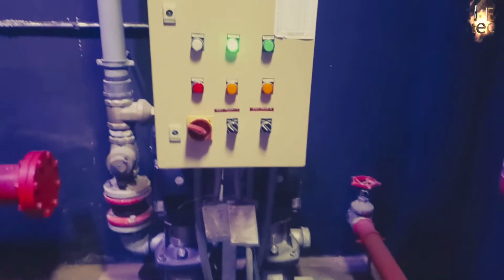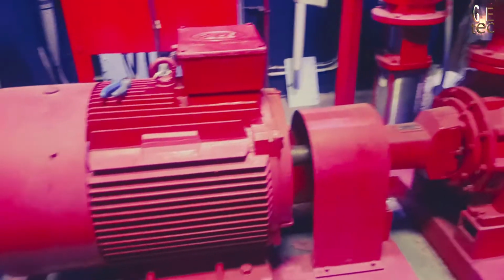Secondarily, this pump prevents sprinkler systems from being damaged when the fire pump begins sending water. If a system does not have a jockey pump keeping it pressurized, it may have a relatively low pressure. When the fire pump starts sending highly pressurized water through the pipes, the sudden change in pressure can damage or destroy the system.